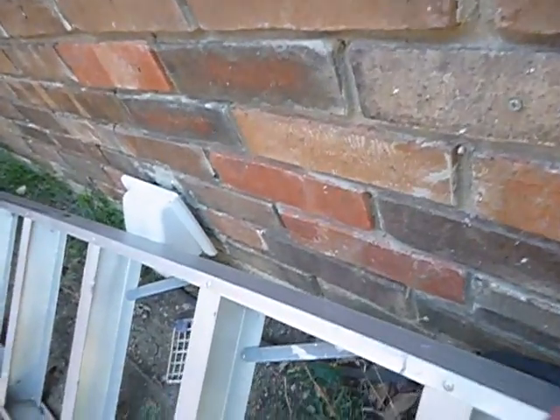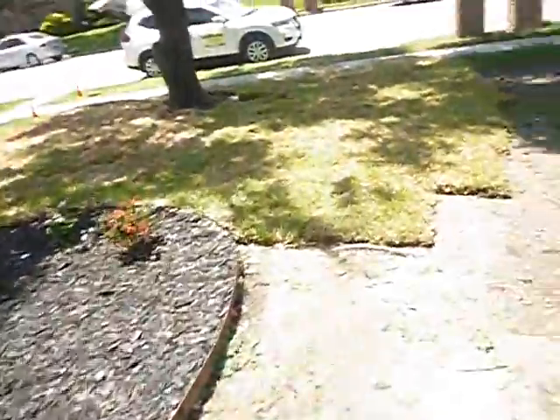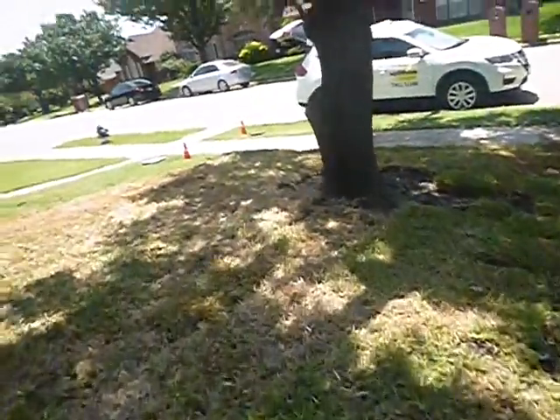This is the clothes dryer vent. The clothes dryer is in operation. I'm going to come back and put this back because it fell off when I was looking at it. But that little screen right there, it doesn't belong on there. That screen will, see what it's doing is catching lint. And it'll continue to catch lint. That'll be a problem for you.